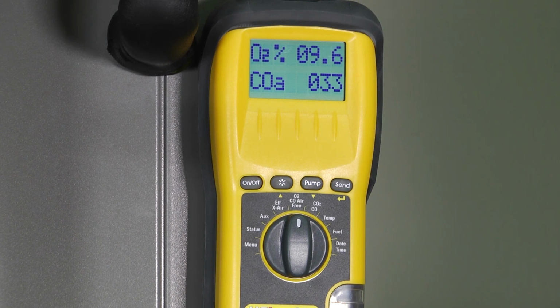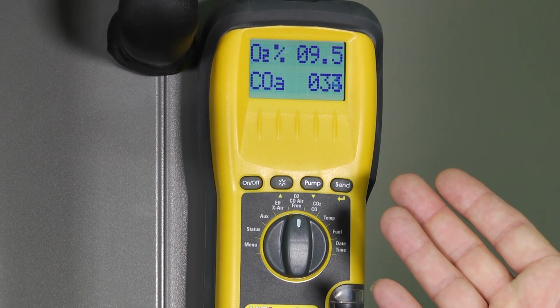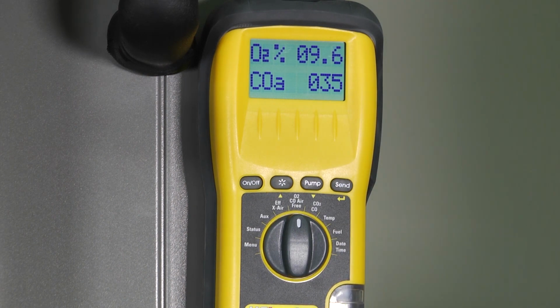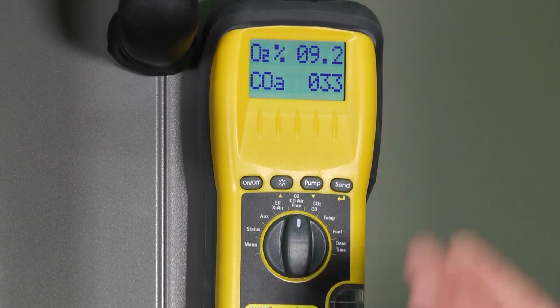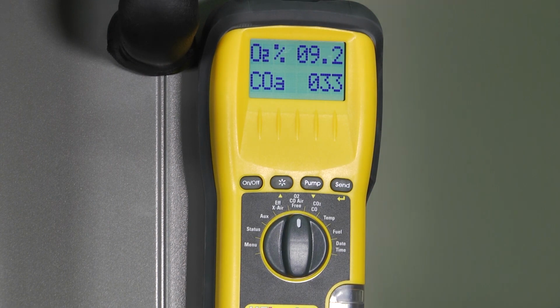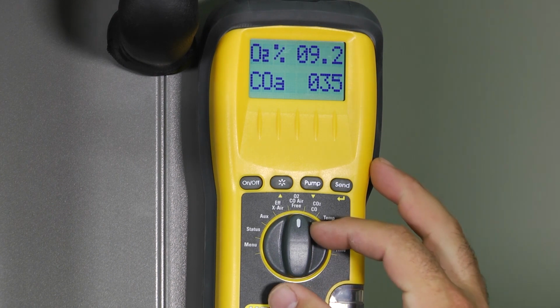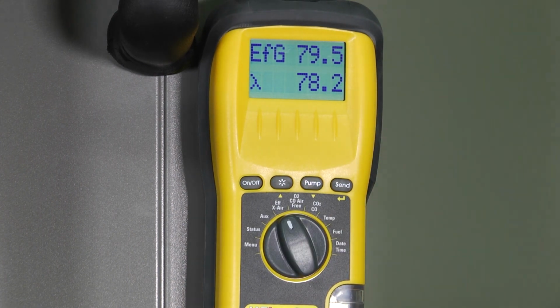So in this case, as long as those flue gases never reach inside my room, I'm not going to have an issue. But now you say to me, Mark, how does it tell me whether or not I have a cracked heat exchanger? Great way of saying it: the fan's turned on right now. If my O2 level was higher than that, I would know that I'm getting excess air somewhere. I can flip over to the next one.